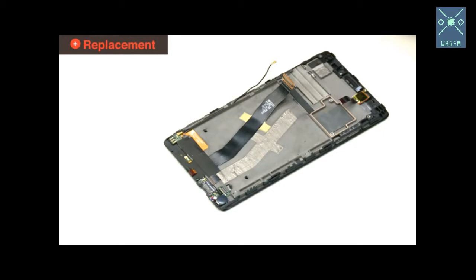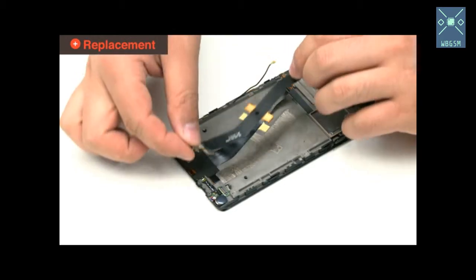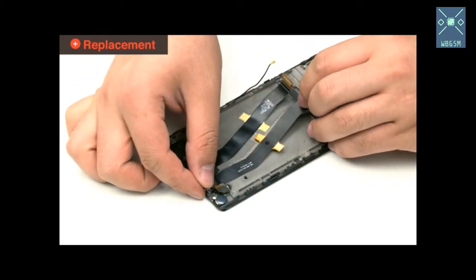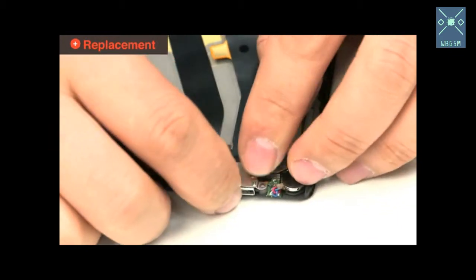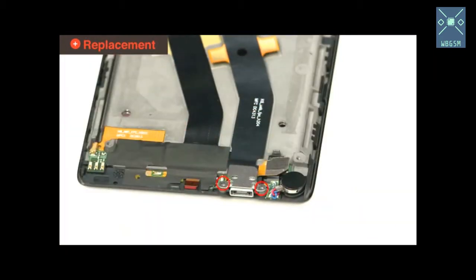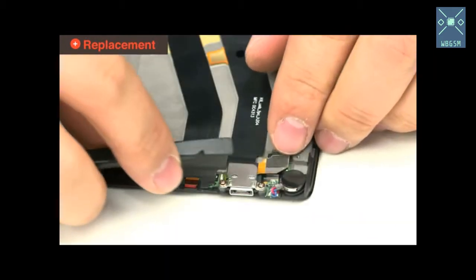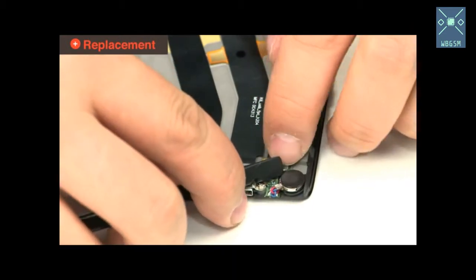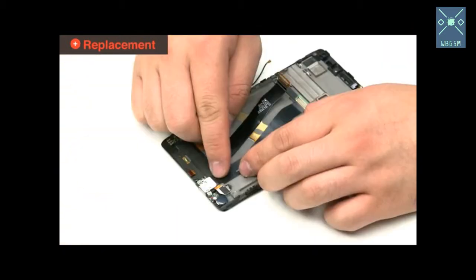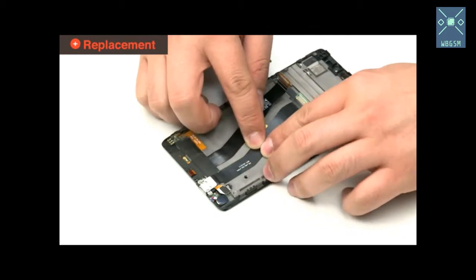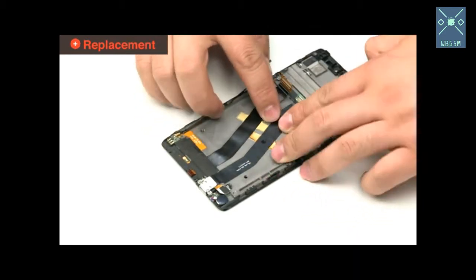Replacement. USB port assembly. Place the USB port assembly into position. Replace the 2 screws to secure it. Reattach the I/O board connector. Press along to properly apply the adhesive backing of the ribbon cable.